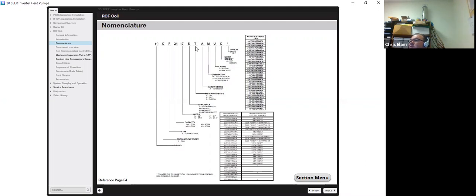The next one is your T. This is what you're going to see with a regular TXV. If you have an E, that's going to be an EEV. Your A is your major series. Your M indicates that it's a multi-position coil. And here, this is a U, so that stands for uncased. If it was a C, it would be a cased. Your last one here, this is a C. It's your minor series.